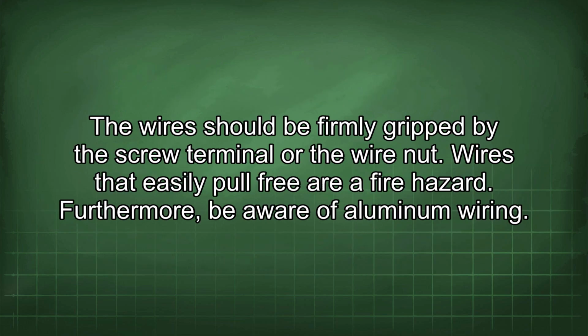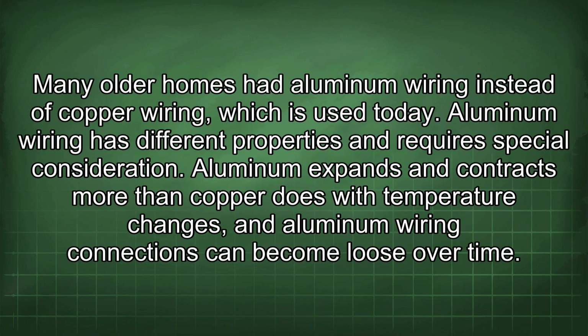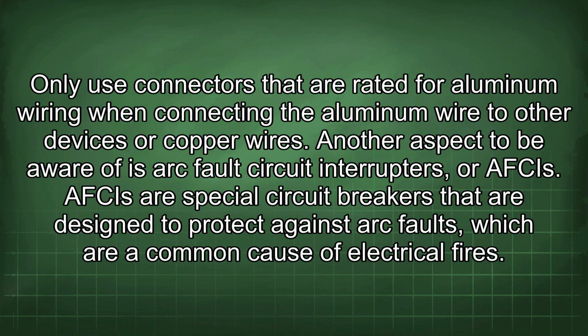Furthermore, when you are inspecting the electrical connections, ensure to give each wire a tug. The wire should be firmly gripped by the screw terminal or the wire nut. Wires that easily pull free are a fire hazard. Furthermore, be aware of aluminum wiring. Many older homes had aluminum wiring instead of copper wiring, which is used today. Aluminum wiring has different properties and requires special consideration. Aluminum expands and contracts more than copper does with temperature changes, and aluminum wiring connections can become loose over time. Only use connectors that are rated for aluminum wiring when connecting the aluminum wire to other devices or copper wires.